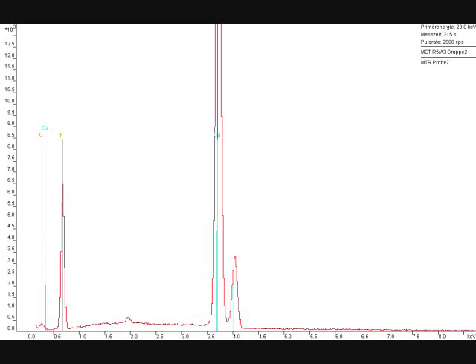And as we discussed before, there may be Auger electrons in the process of filling up the empty shells. And when that happens, those Auger electrons may actually escape the detector, leading to those very specific escape peaks. But how do you know it's an escape peak? Well, the thing is that this escape peak has the actual energy of the parent, like the calcium, minus the energy of the actual silicon K-alpha photon. So that's what determines this as an escape peak. Quite a fascinating phenomenon, I believe. And while that always happens to some extent, you can only see it in very few minerals, because the magnitude of that escape peak is also dependent on the actual composition of the materials. So this is a very rare sight to be actually able to see this clearly.